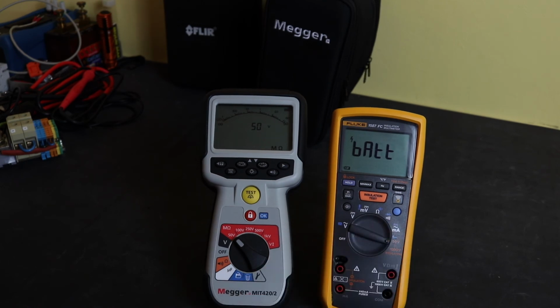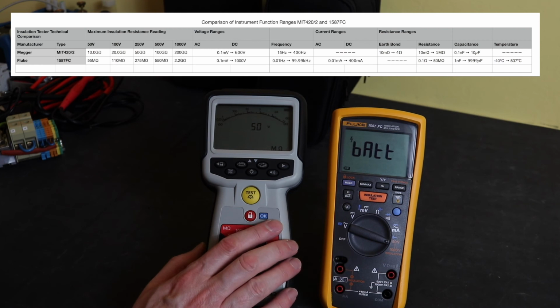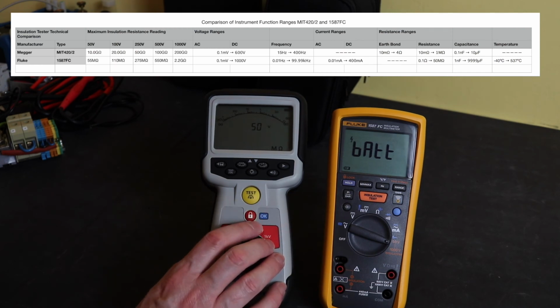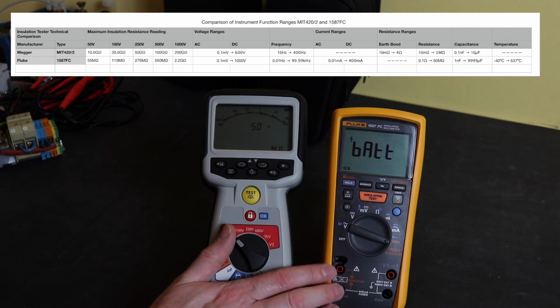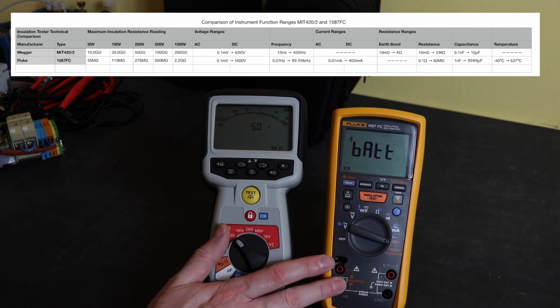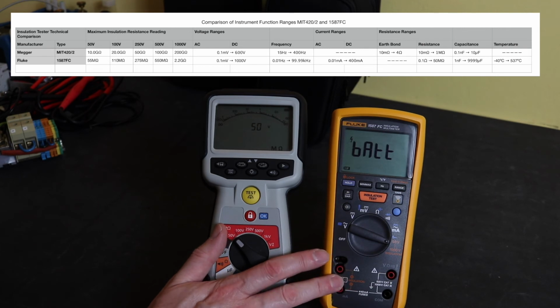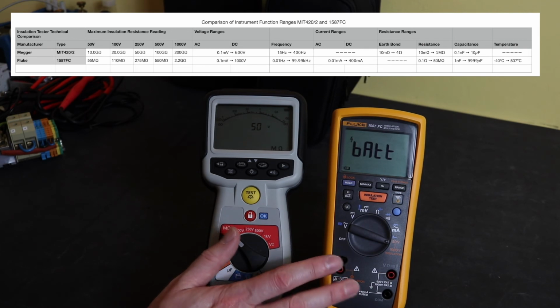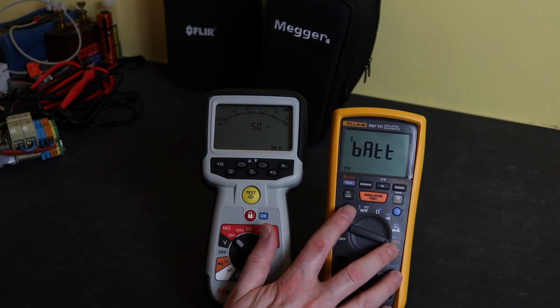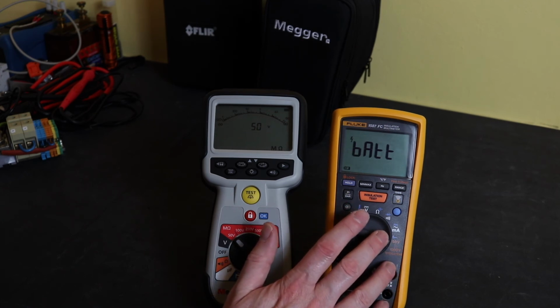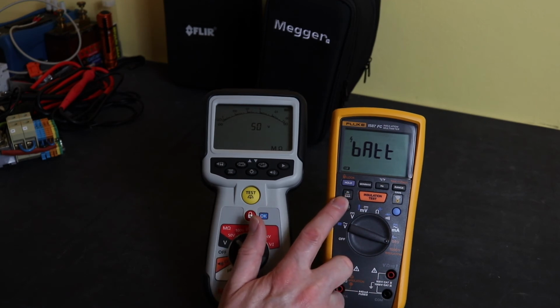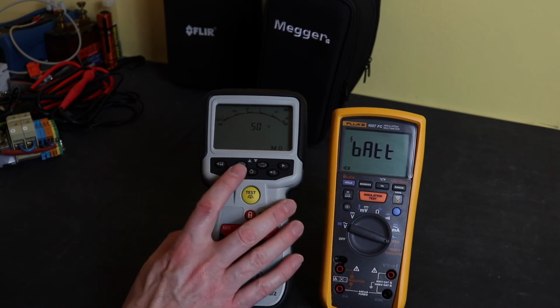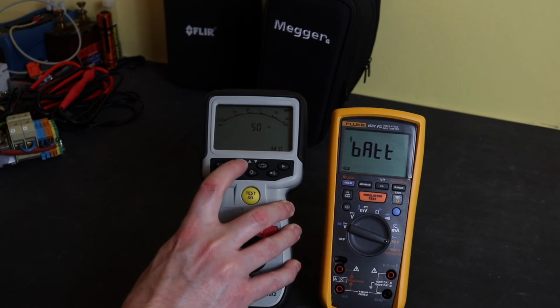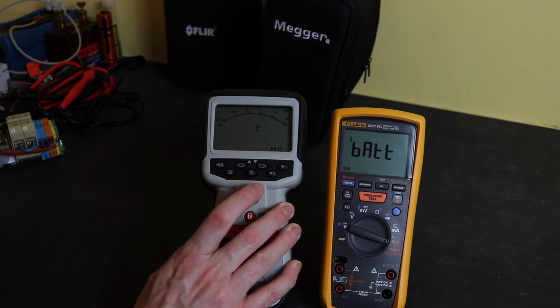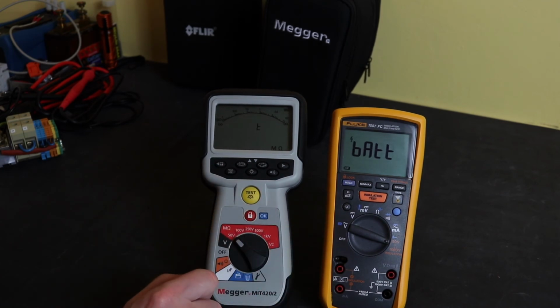So in terms of insulation test capabilities, the Megger here, 200 gigaohms at 1000 volts, drops down to 100 gigaohms at 500 volts. In contrast, the Fluke here, 2.2 gigaohms at 1000 volts and 550 megaohms at 500 volts test voltage. In terms of additional functions for the 1587, you get PI and DAR up here, and you also get PI and DAR on the Megger. You also get a standard time function as well that you can set off the settings menu down here.